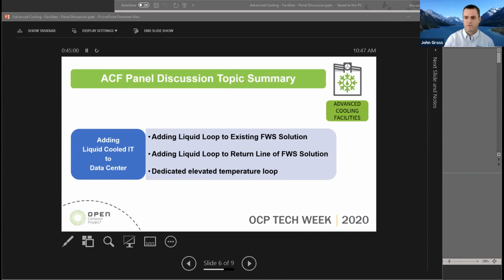Yep. And the other thing that I'll add is, as we've been going through the conversations today, even since the opening, our focus has been on processors. We haven't even really talked about GPUs and DIMMs for memory, and workload dependent. Those different chips can have different requirements, or they can be the critical temperature in the solution. What we haven't talked about is things like networking and storage. And one of the challenges when you start factoring those pieces in is that a lot of times the networking and storage hardware is not compatible with those ultra high temperatures.